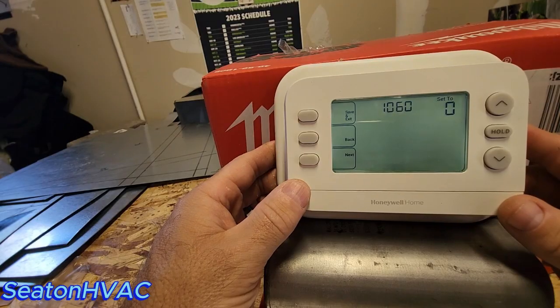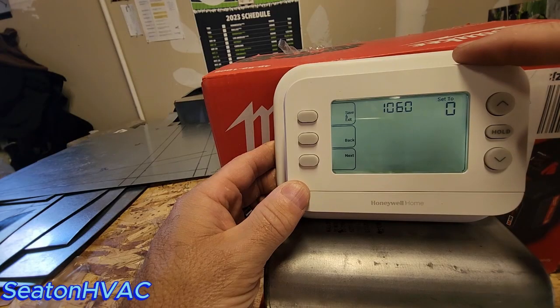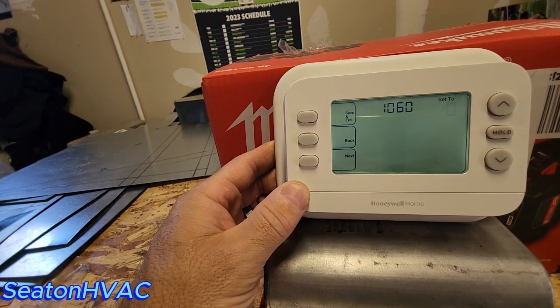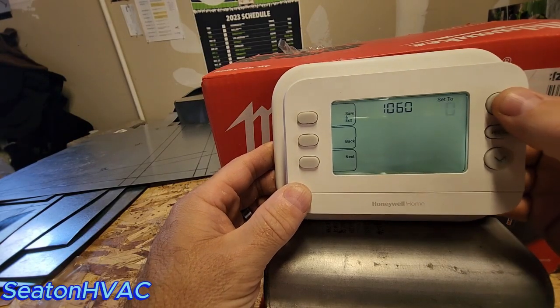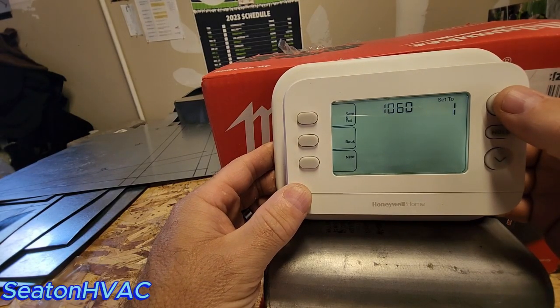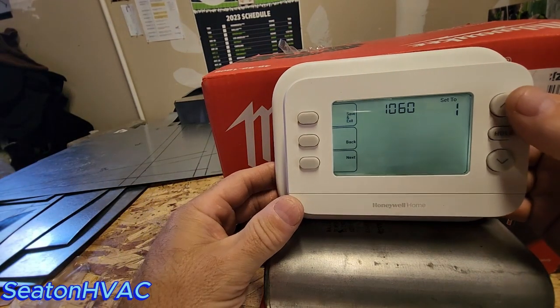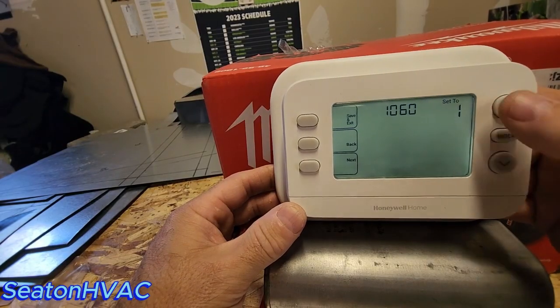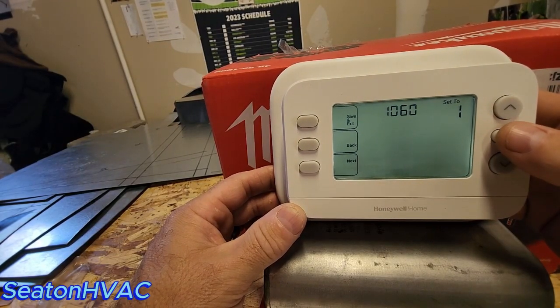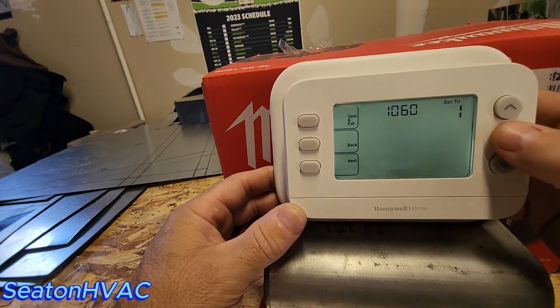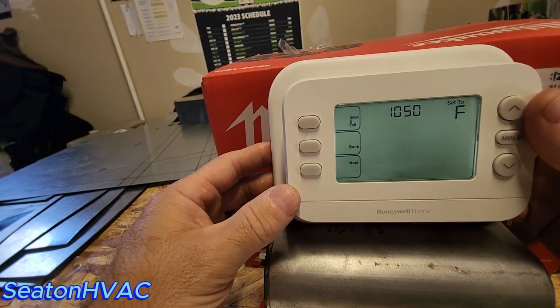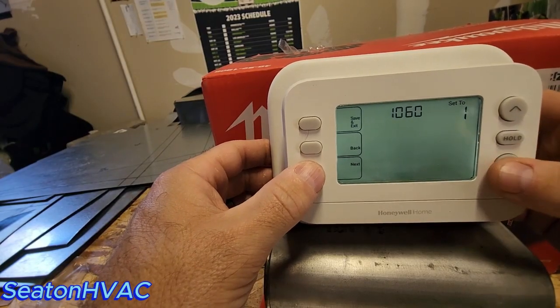1060, that's whether or not it has an outdoor sensor. If you're using one of the 2-wire sensors, and this does work with the same 2-wire sensors that the old Vision Pros and the Prestige thermostats used. 0 would be no outdoor sensor. 1 would be wired outdoor sensor, meaning you have the 2 S terminals wired in. And if it was the Wi-Fi, it would have a 2 here, and it'd say internet only. Internet would control the backup stages. So let's go back out of that. Next. So we're going to leave that at 0.